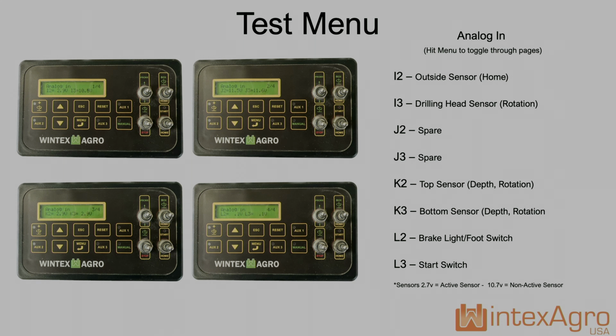Analog in is going to tell you the voltage there. When a sensor is active, you're at 2.7 volts; when it's not active, you should be at 10.7. If you're anywhere in between 2.7 and 10.7, your sensor or the cable to it is bad.